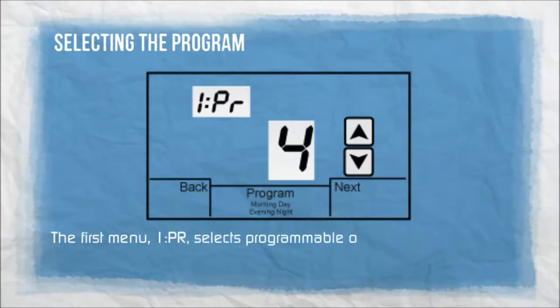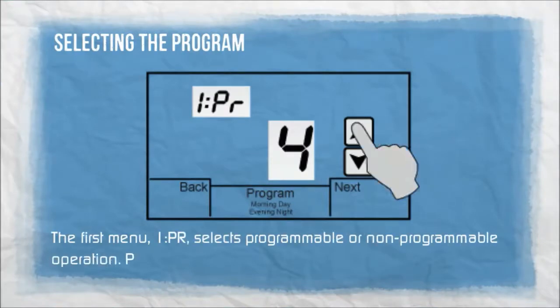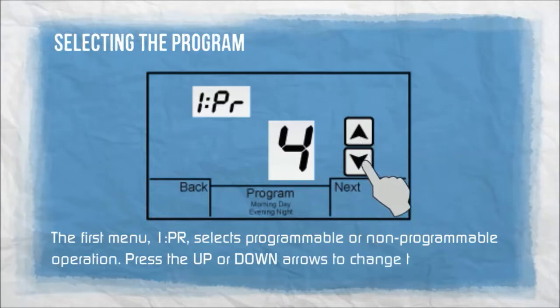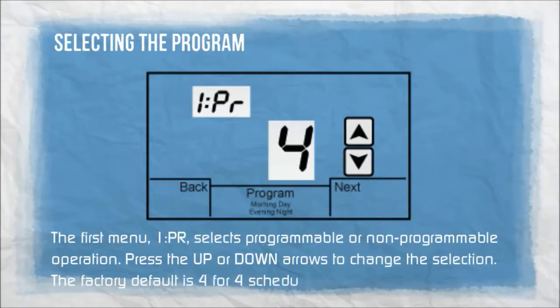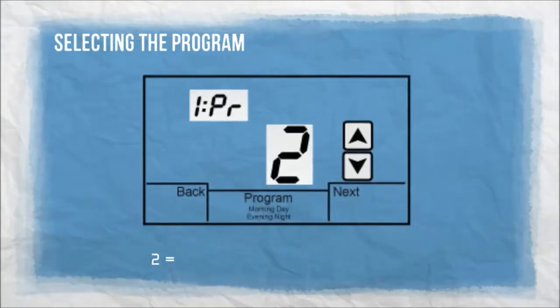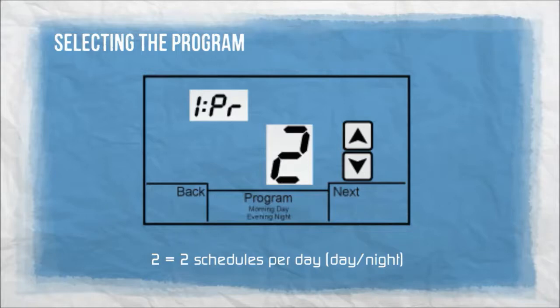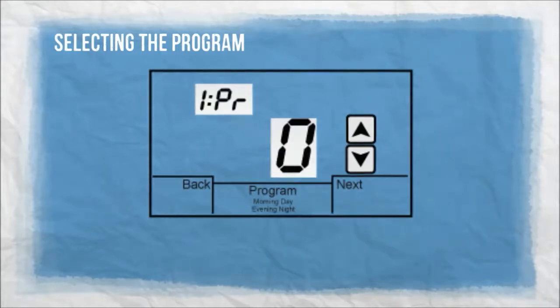The first menu, 1PR, selects Programmable or Non-Programmable Operation. Press the up or down arrows to change the selection. The factory default is 4 for 4 schedules per day. 2 is for 2 schedules per day — day, night. 0 is for manual mode, non-programmable.